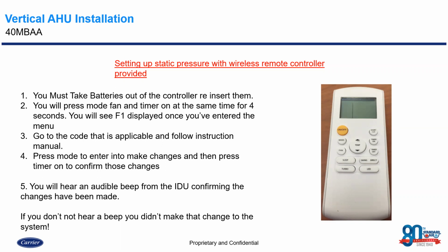So one, you're going to need to grab your wireless controller, which you'll see on your right here, which is the RG57 wireless remote controller. Now this remote controller has an advanced service feature function on it that we can get into and set up the static pressure either manually, or we can do an automatic airflow. So in order to get into this advanced service menu, what you're going to need to do is take the backside off of this wireless controller and remove one battery. Once that battery is out, you want to then go ahead and hit the on and off button to clear the screen like you see it depicted in this slide. Once the screen is clear, go ahead and put your battery back in and put the cover on.